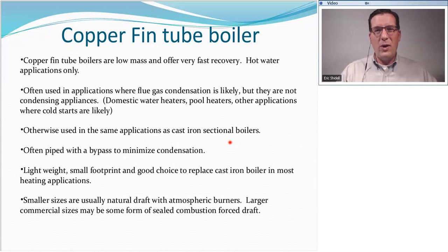That's a way a lot of companies like to go, to pull out the cast iron and go back with the copper fin tube, because they're so much lighter and easier to place and easier to fit into a space. And they take less time because you don't have to put them together like a lot of cast iron sectionals. Because of this condensation issue, they're often piped with a bypass. In fact, almost all copper fin tube boilers, if you read the installation instructions very carefully, must have a bypass installed. And this is one of the problems that you'll experience.